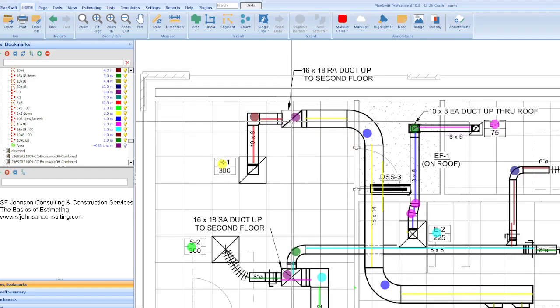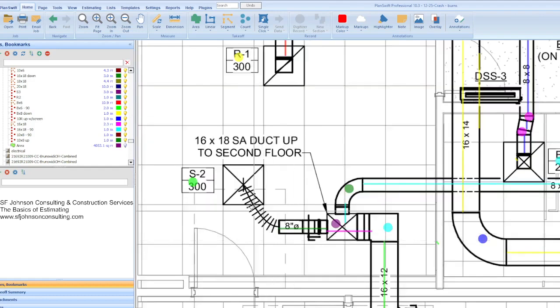Your ductwork is rigid, so you have to have straight pieces and then connect it to 90-degree pieces, and it's not flexible. The only portion of flexible ductwork you can allow to use are at the grills, and this is a symbol for a flexible ductwork, and it's usually no more than like 5 feet, max 3 to 5 feet. So that's what that means.